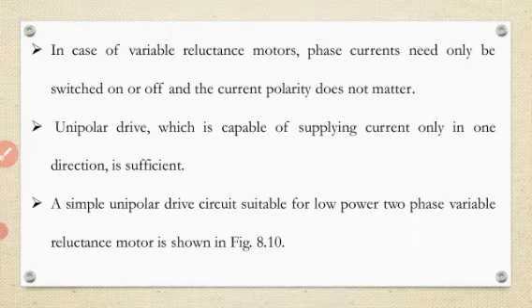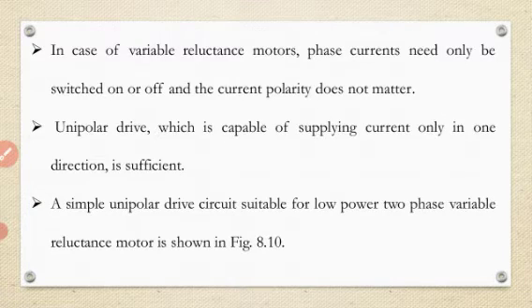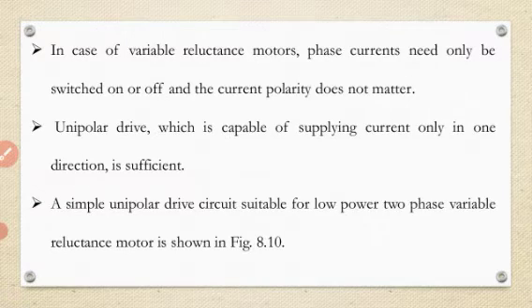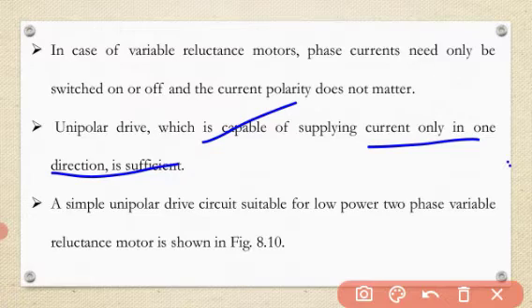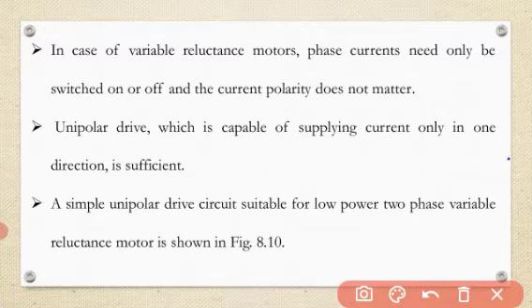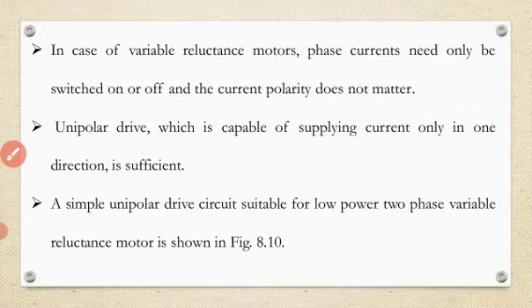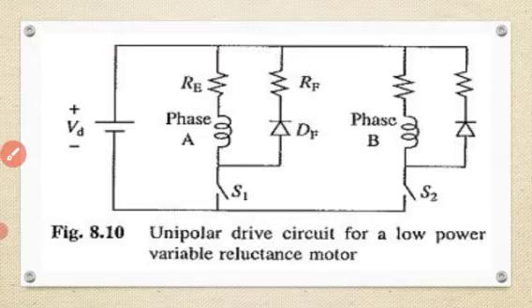In the case of a variable reluctance motor, phase currents need only be switched on or off, and the current polarity does not matter. A unipolar drive, which is capable of supplying current only in one direction — as the name indicates — is sufficient. A simple unipolar drive circuit suitable for a low power two-phase variable reluctance motor is shown in the next figure.